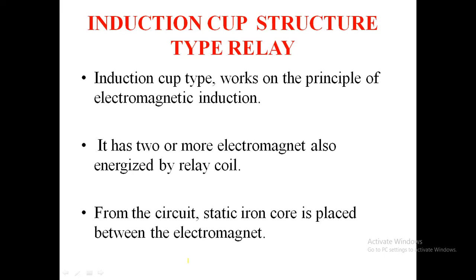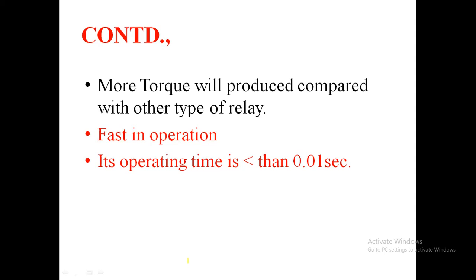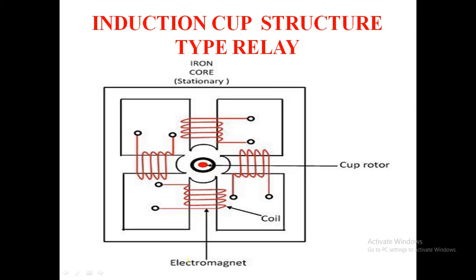Next, coming to the induction cup type relay. This mainly works on the principle of electromagnetic induction. It has two or more electromagnets energized by the relay coil. The coil is wound on the electromagnet which generates a rotating magnetic field. Because of this rotating magnetic field, current is induced inside the cup, and the cup starts rotating. This produces more torque in the cup type induction relay compared to the other relay types.